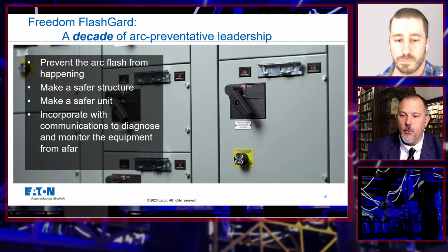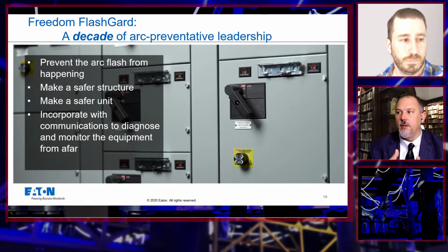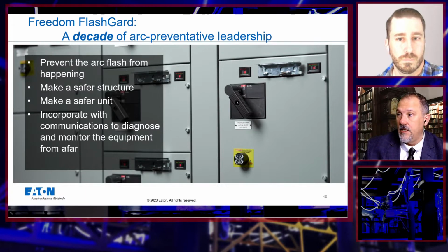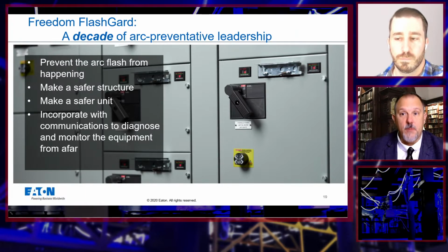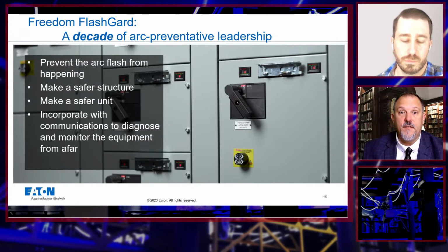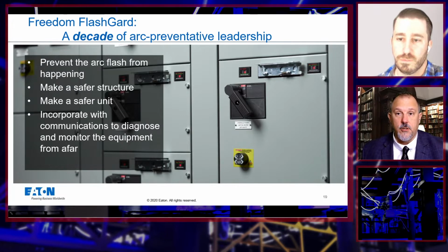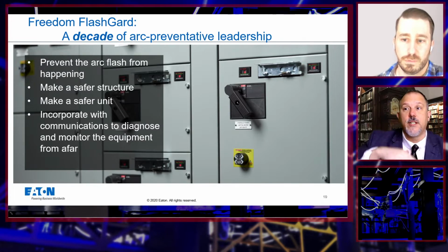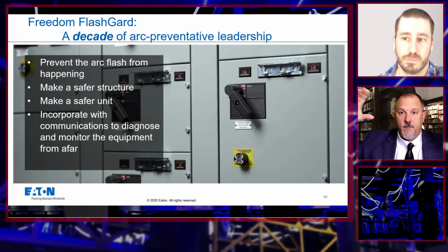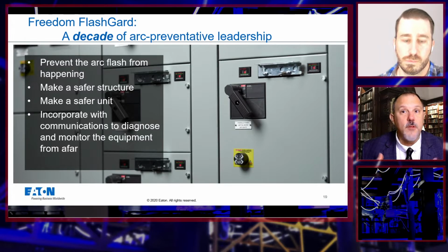I think a point was made about maintenance, making sure we're performing it, and the moment you open certain compartment doors - that's the other thing, you got to really be trained to understand what doors you're opening and what your exposure is. Because if you open the wrong door, you've defeated the arc resistant nature of that solution. I might be able to address lower voltage when I open the control panel compartment because I know nothing's going to intrude there, but if I opened the wrong door, that would be bad.